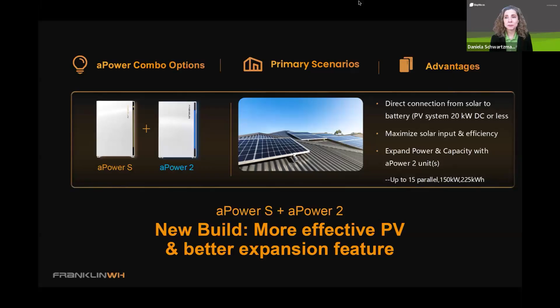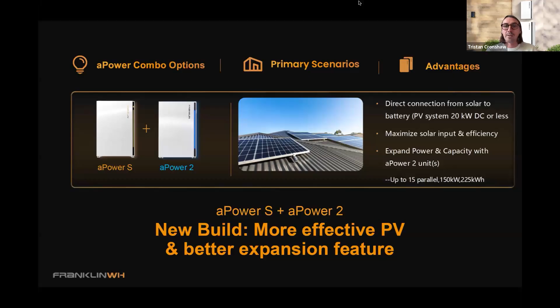Going back to some combinations, we get a lot of questions about when to use an aPower S and aPower 2. Maybe you need a lot of capacity for a specific desired duration when the customer is off grid, or to get them through a peak rate period, but they have a nominal solar system, say just 10 kilowatts of PV. That works great connected to a single aPower-S, and then they can scale out with aPower2s. It wouldn't make sense to use multiple aPower-Ss in that case, since you can utilize a single inverter from one aPower-S and scale with the aPower2.